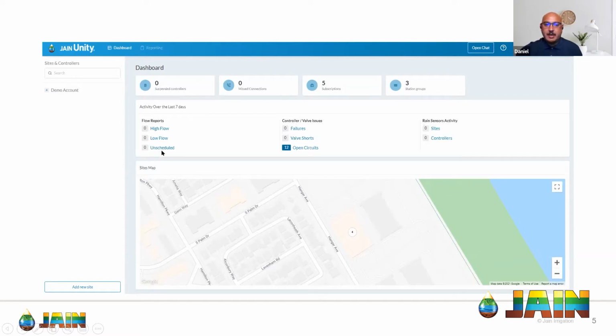One of the nice features here is our activity over the last 7 days. So if your system's tied to a flow sensor, we can let you know if it's a high flow, low flow, or unscheduled flow. If there's a broken sprinkler, the system's going to send you a high flow alert. Maybe you had a broken pipe, same thing, it's going to send you a high flow alert. A low flow alert could be maybe a valve didn't open all the way, or nozzles got clogged. Maybe the valve failed hydraulically completely, so you would know, hey, I've got a station out there not running the normal learned flow of the system. And then an unscheduled flow. If the system sees water flow through that flow sensor when it's not issuing a watering command, the system will alert you.